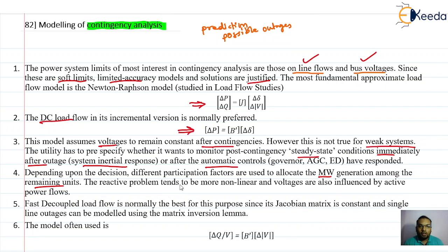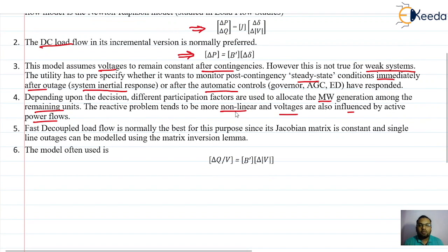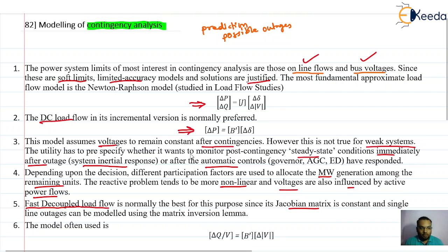Reactive problems tend to be more non-linear and voltages are also influenced by active power flow. From the decoupled load flow method, we can go further to the fast decoupled load flow method. The problem with the decoupled method is inverting the Jacobian at every iteration; in the fast decoupled method, using the matrix inversion lemma, the Jacobian is made constant. This fast decoupled load flow model can also be utilized for contingency analysis, and the modeling choice depends on what parameters and conditions the utility wants to monitor.